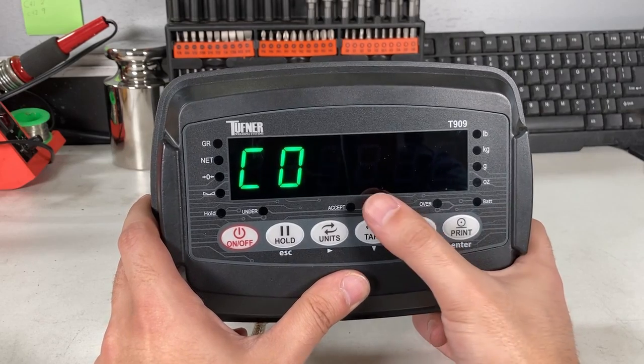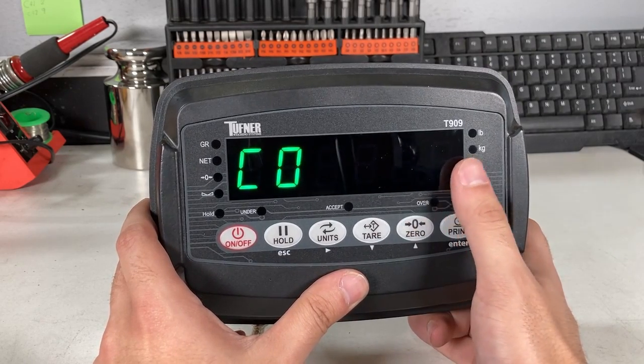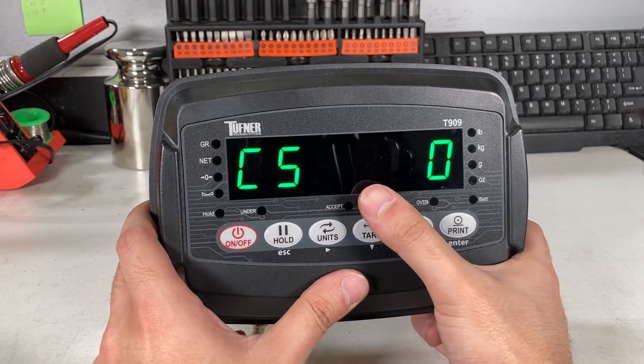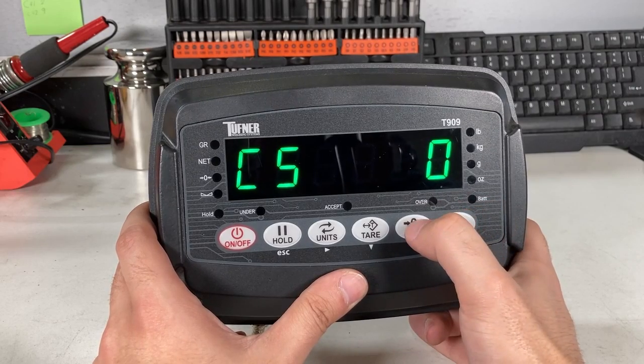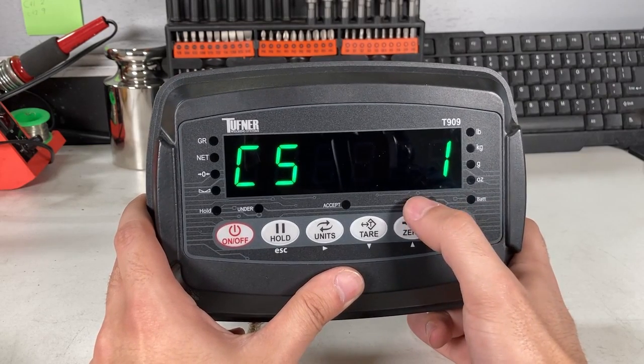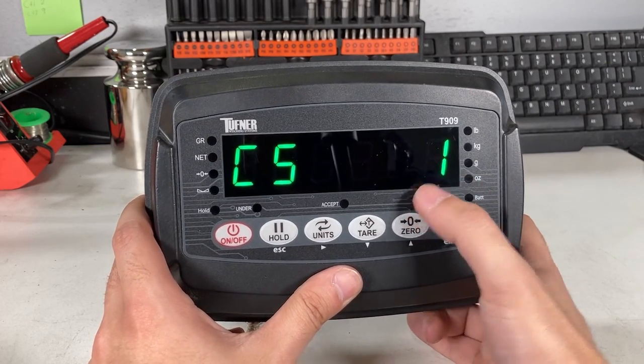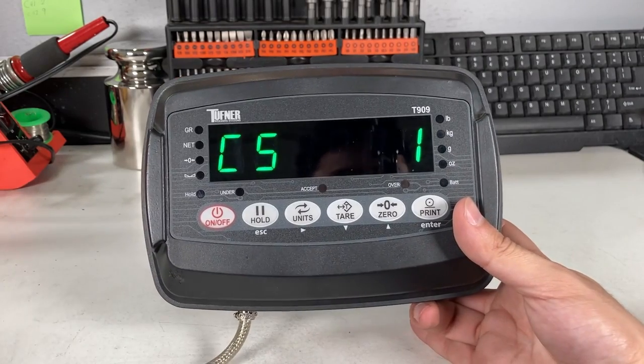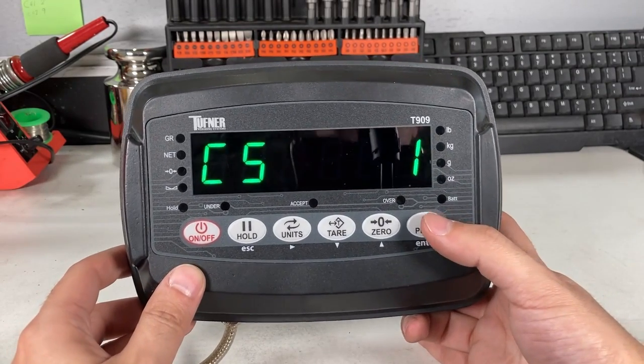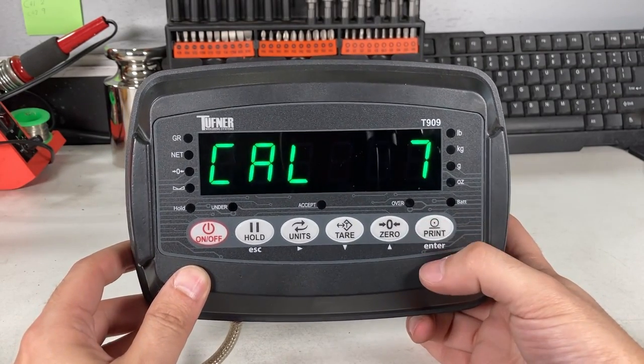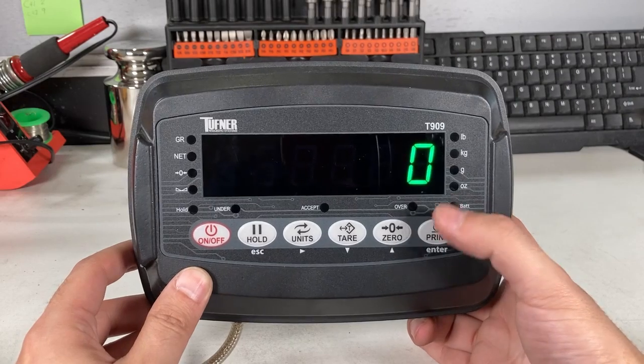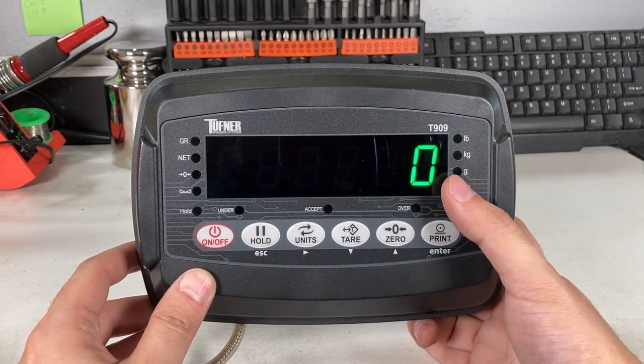Let's print. C05 is the 0 calibration, so press print. C50, press the 0 button to make it 1. Now make sure there's nothing on the scale. Remove all the weight, because it will zero out the weight on the scale. Now press print. Cal 0. 0 is good because there's no weight on the scale.